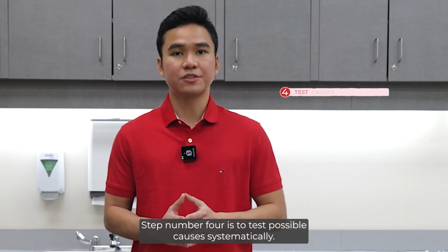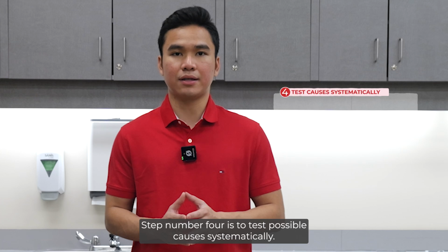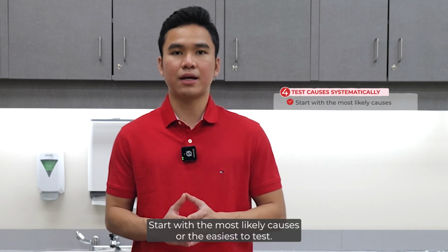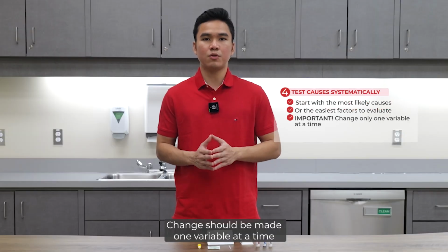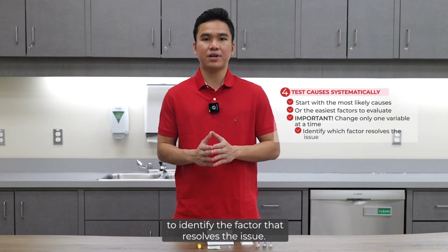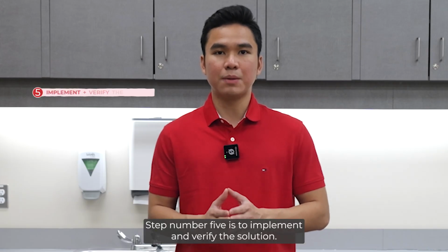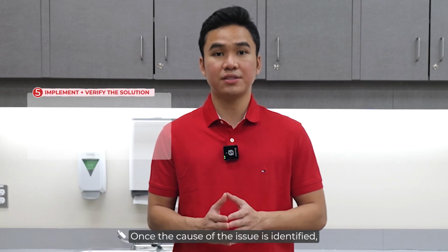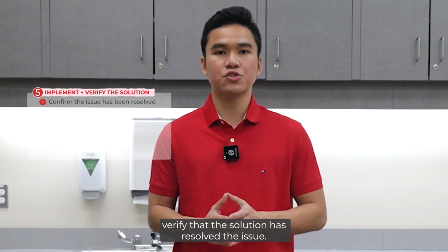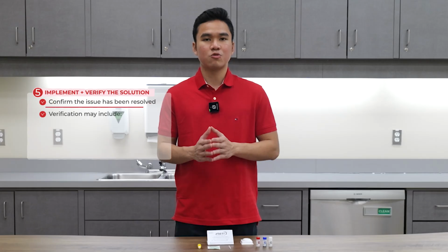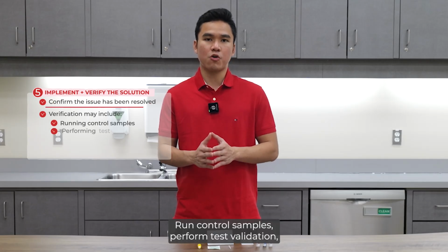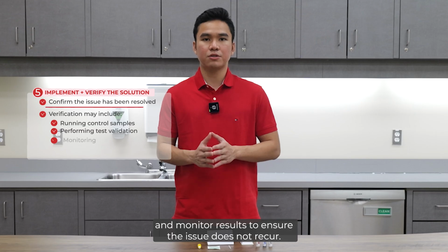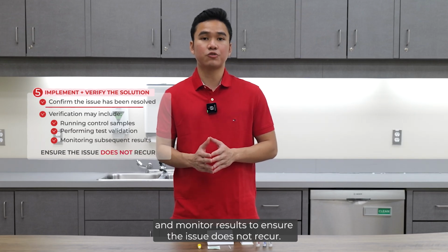Step number 4 is to test possible causes systematically. Start with the most likely causes or the easiest to test. Change should be made one variable at a time to identify the factor that resolves the issue. Step number 5 is to implement and verify the solution. Once the cause of the issue is identified, verify that the solution has resolved the issue. Run control samples, perform test validation, and monitor results to ensure the issue does not recur.